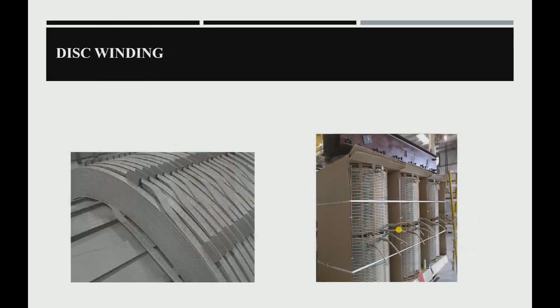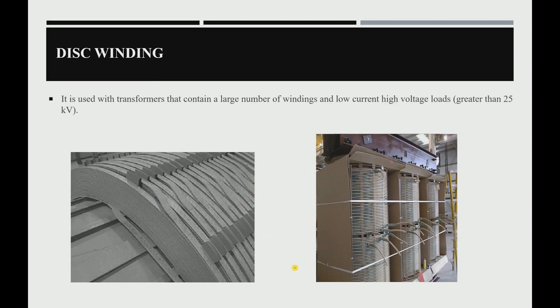The second formation is called the disk winding — as if we have a group of disks around the transformer core. This type is used with high power rating transformers, when we have a large number of turns and low current, or more specifically, high voltage loads greater than 25 kilovolts.